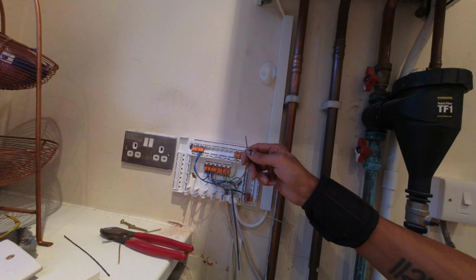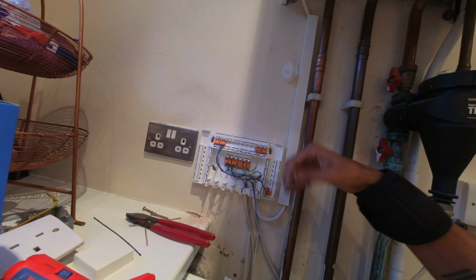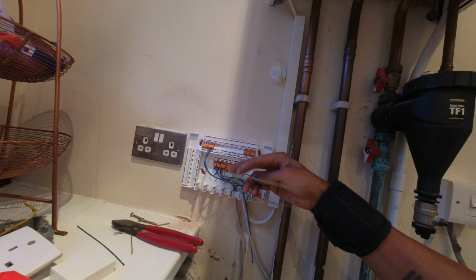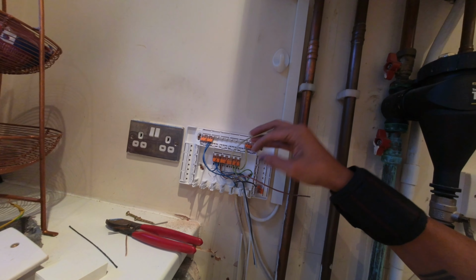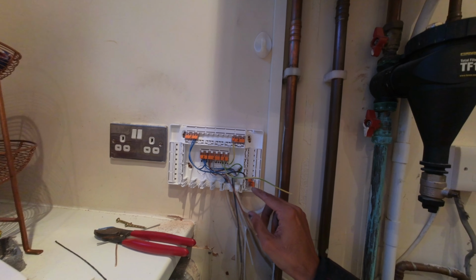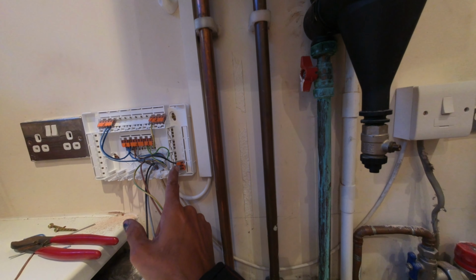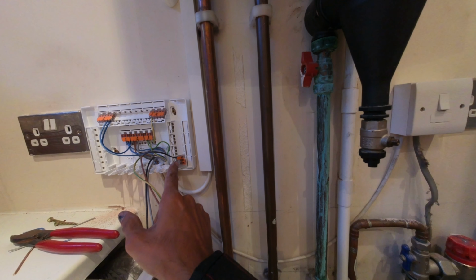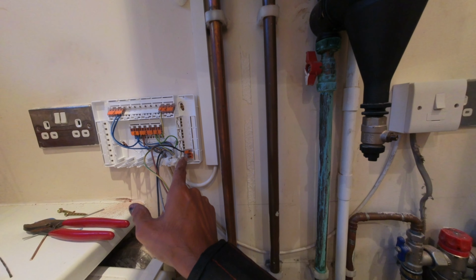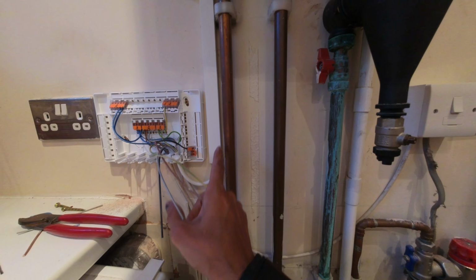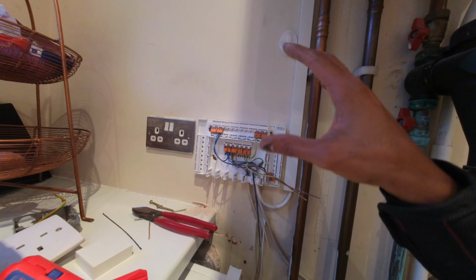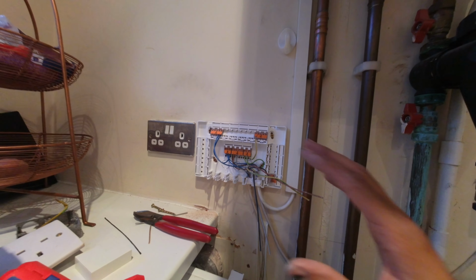That will go into a 2-way Wago with that. The earth, obviously I need to pop the earth into there. The black I'm using as my switch live, so I've put a 3-way Wago there, so that's going to contain the 2 switch lives from each of the zone valves, and then the third one is going to be the one going back to the boiler. So that's sort of the way I'm doing it. I'm just doing it in stages.